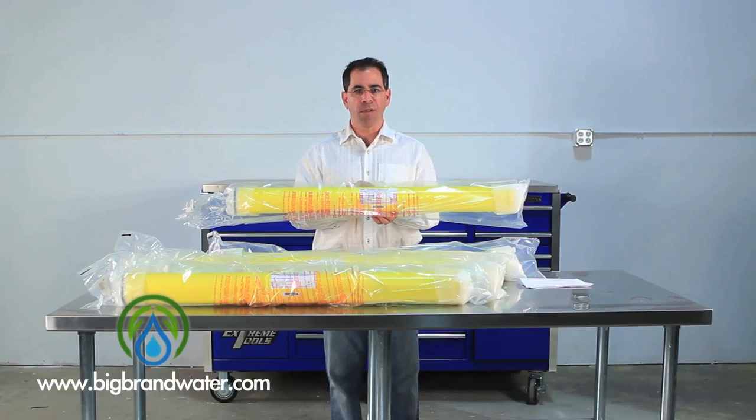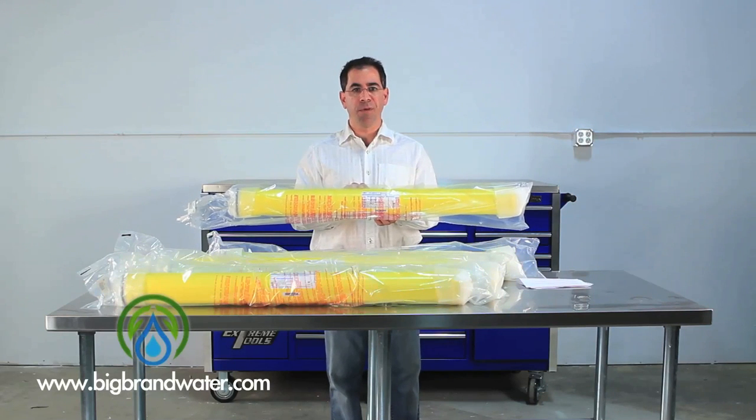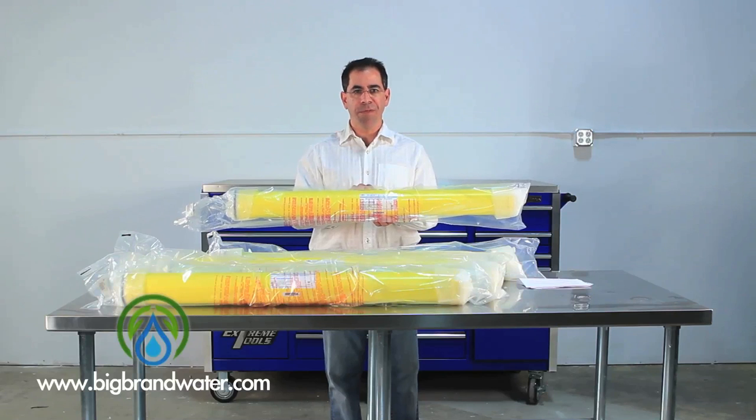What that means is as the water gets colder, you're going to get less production with the same pressure.